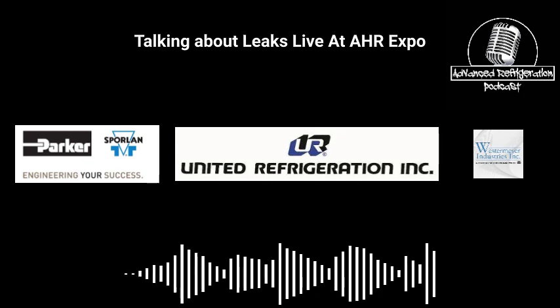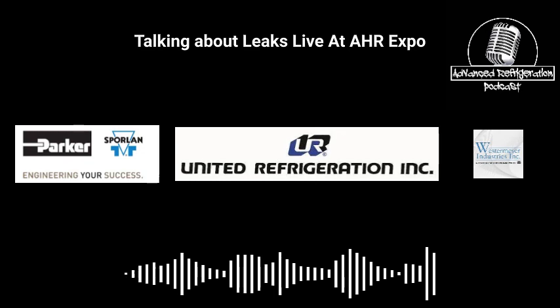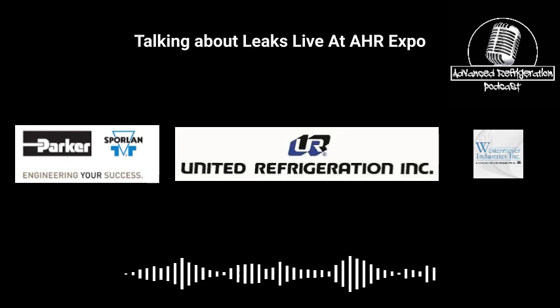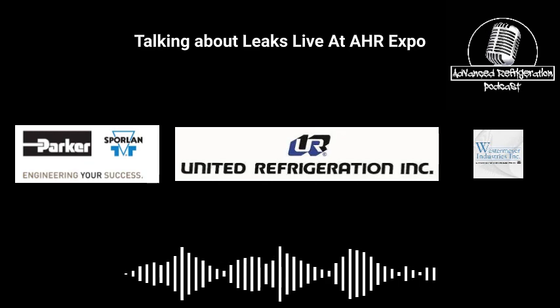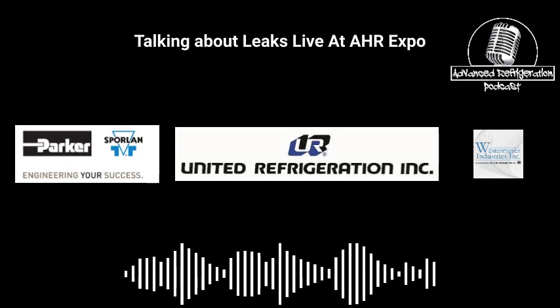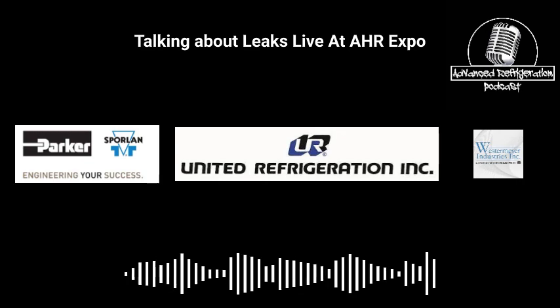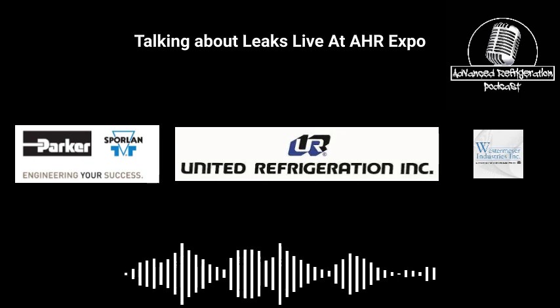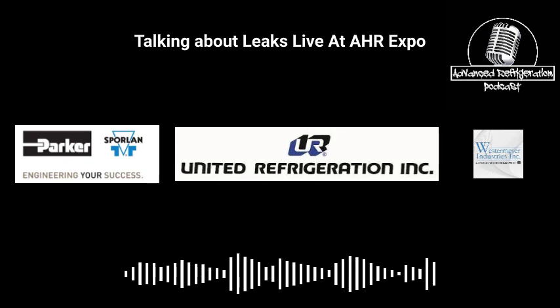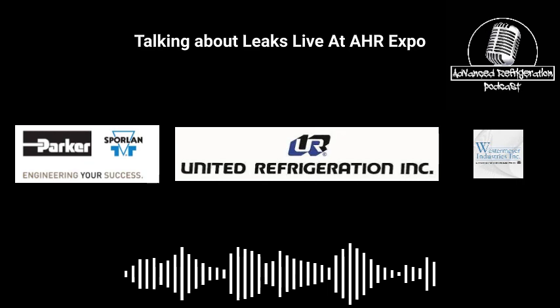So certain compressors, usually it's like 46 to like 47 hertz. It's like usually one I delete out of all of them, because generally in my experience, that hertz range on medium temp compressors on the TC side just vibrates like an old car. So what you want to do is test this, and you need to go hertz by hertz. So go 1 hertz at a time, up and down, till you find where this vibration starts and stops. And then in every VFD that I've seen so far, you could delete ranges of frequency out, so that way you don't vibrate that compressor.